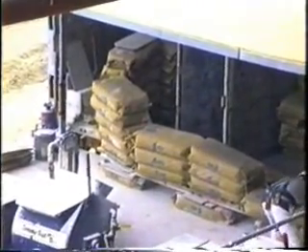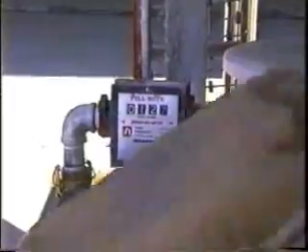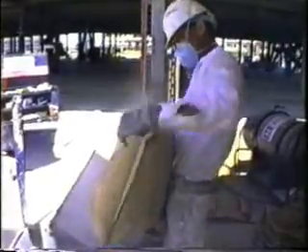Mixing of the material should be in accordance with the recommended application guidelines. There are several types of mixers that can be utilized with CAFCO materials and are approved for use. Most common are paddle and ribbon type mixers. The contractor must ensure that the mixer is operating at speeds of 35 to 40 revolutions per minute.